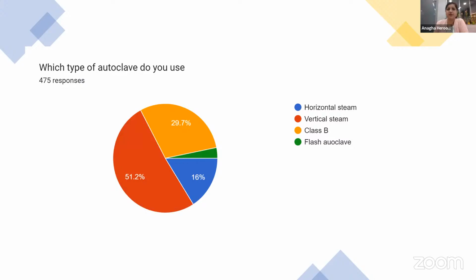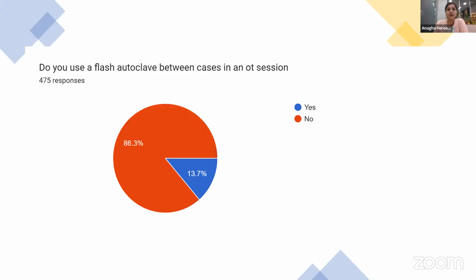Regarding type of autoclaves, we had a great amount of discussion yesterday, where it was almost decided, and it was almost recommended that Class B autoclaves are absolutely important because they have the vacuum and the pre-vacuum stages for complete air removal. As we can see here, almost 30% are using Class B, but 51.2% are still using only the vertical steam autoclave. So this could be an important take-home message.